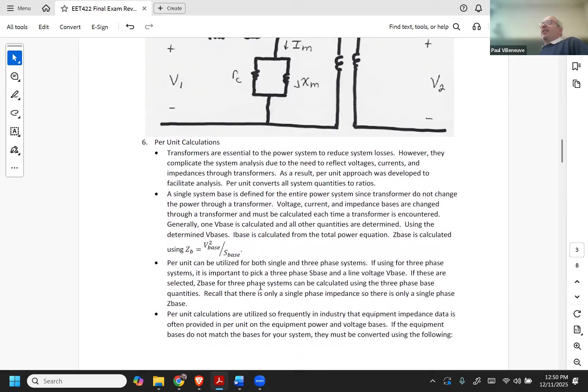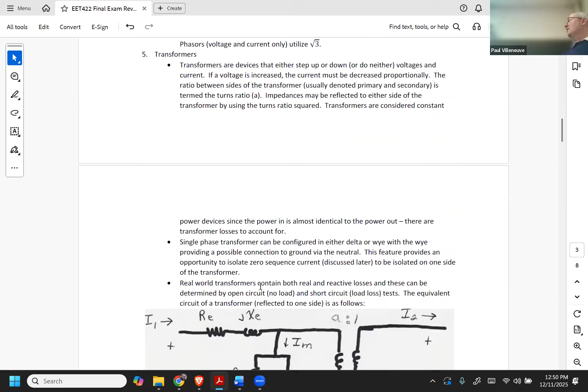So we're going to do everything in per unit. Notice in this description you didn't see much discussion about how you convert currents, voltages, or impedances - because if I do everything in per unit, there is no conversion necessary. Doing things in per unit is really the only way to do systems analysis in a power system, because your circuit no longer has transformers represented as devices that step things up or down - they're just shown as an impedance.